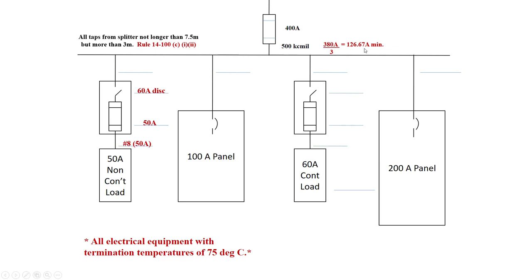Going to table 2 under the 75 degree column, we would have to select a number one. Number ones are good to 130 amp, which is definitely within the one-third of our 500 KC mil. Here's our 100 amp panel and 100 amp overcurrent on it.